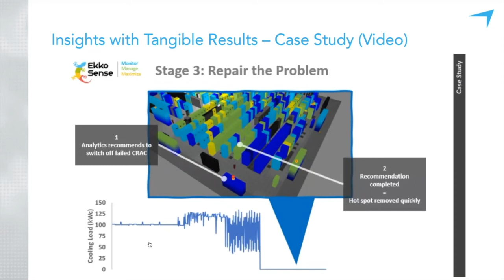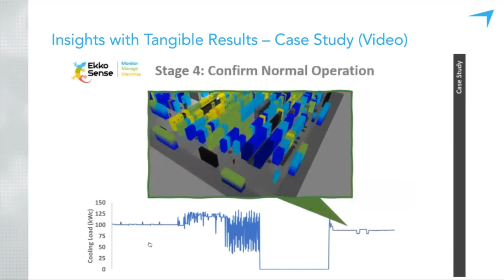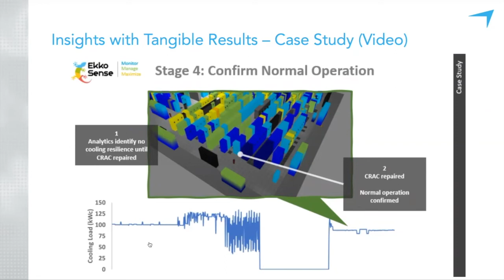The software also gives us the opportunity to really target the fix that's necessary in order to get the site back to normal. So the refrigeration or the maintenance crews are able to forensically look at the historical data in order to target their actions for the fix and then get it back to the steady state operation as it was previously. So that's the first simple case study, just to show you an example of the pre-warning that you can get because you have this historical behavior known.